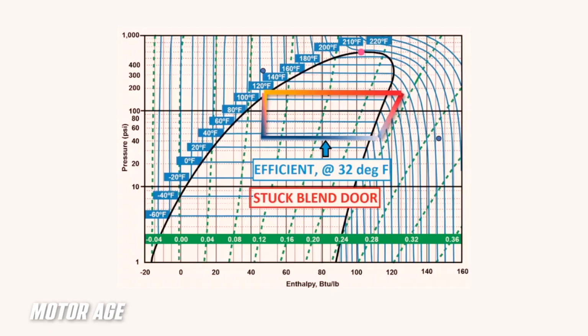So what we have here, this enthalpy chart, are plotted points that represent refrigerant temperature entering the evaporator at about 32 degrees Fahrenheit, just about freezing, which is excellent. This will absorb heat and become a saturated gas, as we see, stepping to the right of the bell curve as saturated gas entering the compressor. The compressor will discharge the pressurized refrigerant, in this case at a pressure of just under 200 psi, and we are still within 2 blue lines of our bell curve, meaning our superheat is just where we want it to be.